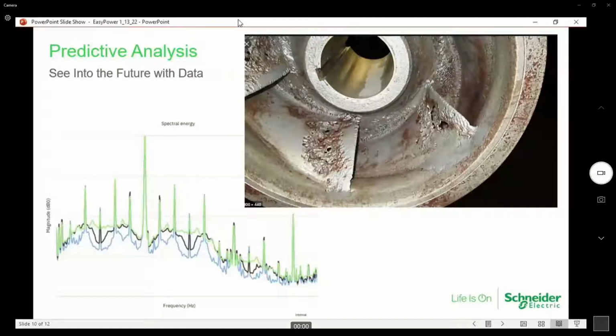It's been cavitating, very, very close to the point of failure. That fault or damage was able to be seen on the graph at the lower left by looking at a combination of harmonic data and vibration. By doing some analysis over time, we can see there's degradation happening and that this thing's about to fail. How valuable is it to say, you've got a pump buried in the ground somewhere, it's failing, we need to get it fixed at an appropriate time, versus waiting until it fails and then we've got an emergency outage.